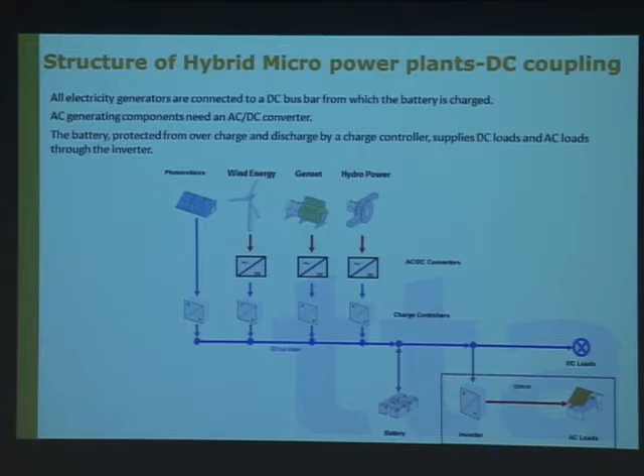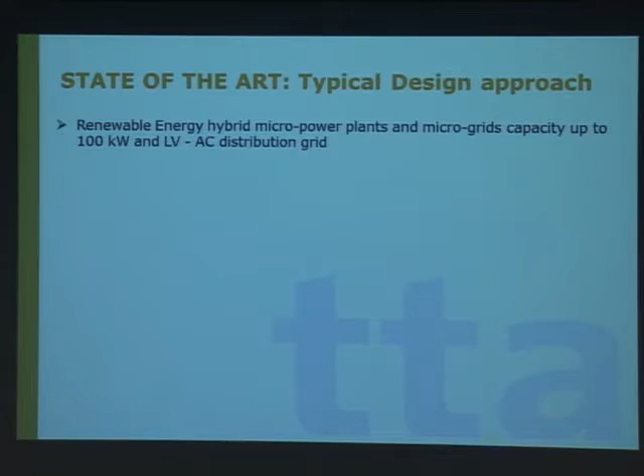In our rural world, we call a microgrid typically up to 100 kilowatt or kVA. But more than the power, it's the concept. Usually it's a microgrid where everything is low voltage, where you don't step up the voltage and have long transmission. So it could be 100, but it could be 200 if you have a lot of distributed generation. But that's the order of magnitude.